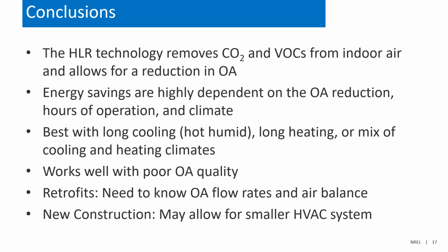However, the energy savings are going to be highly dependent on how much you can reduce that outside air, the hours of operation, and the climate that you're in. Obviously, it's best if you can have a long cooling season, hot, humid climates are especially good for this technology, and a long heating season, or a mix of cooling and heating climates like New York City or Chicago, where you have both high cooling and high heating loads. And it works well if you're in a location with poor outdoor air quality, because now you can reduce the amount of outdoor air that you're bringing into the building.